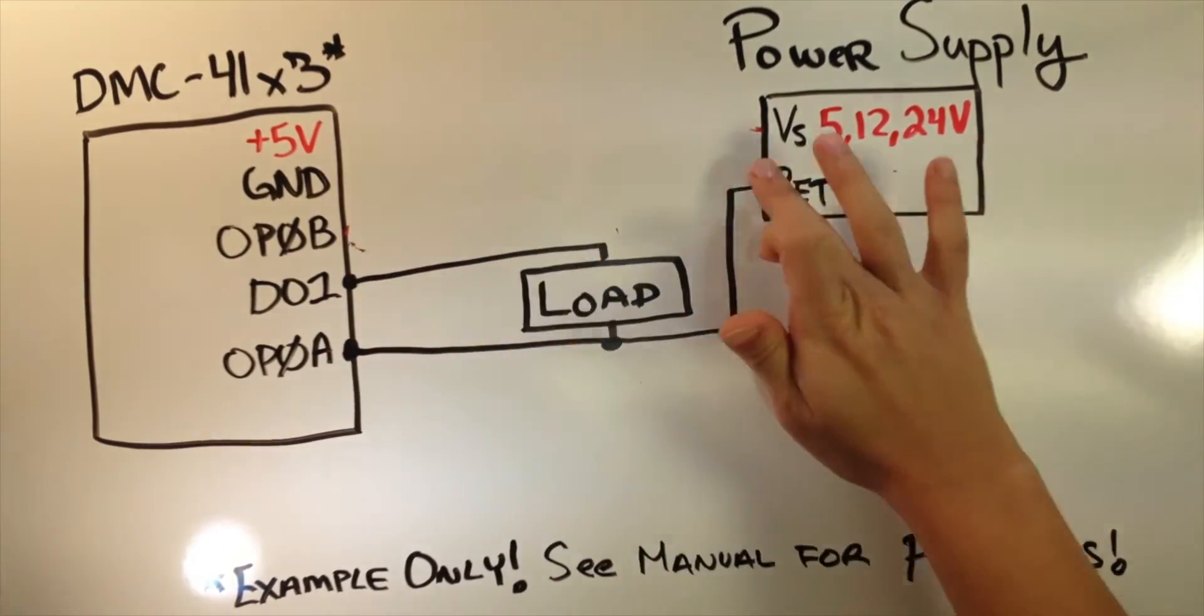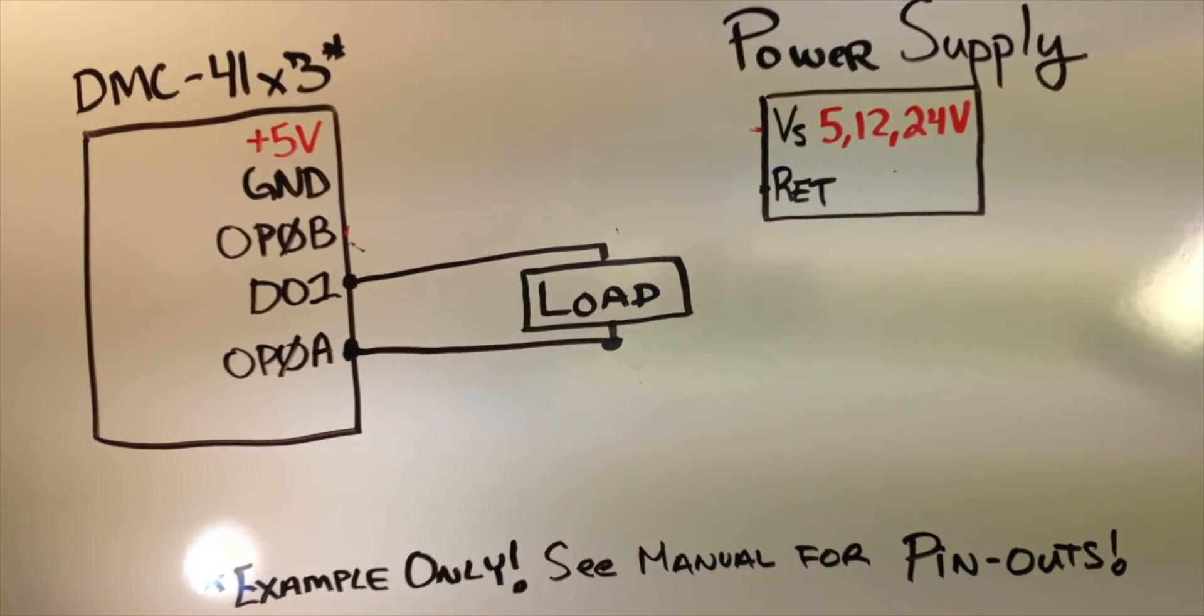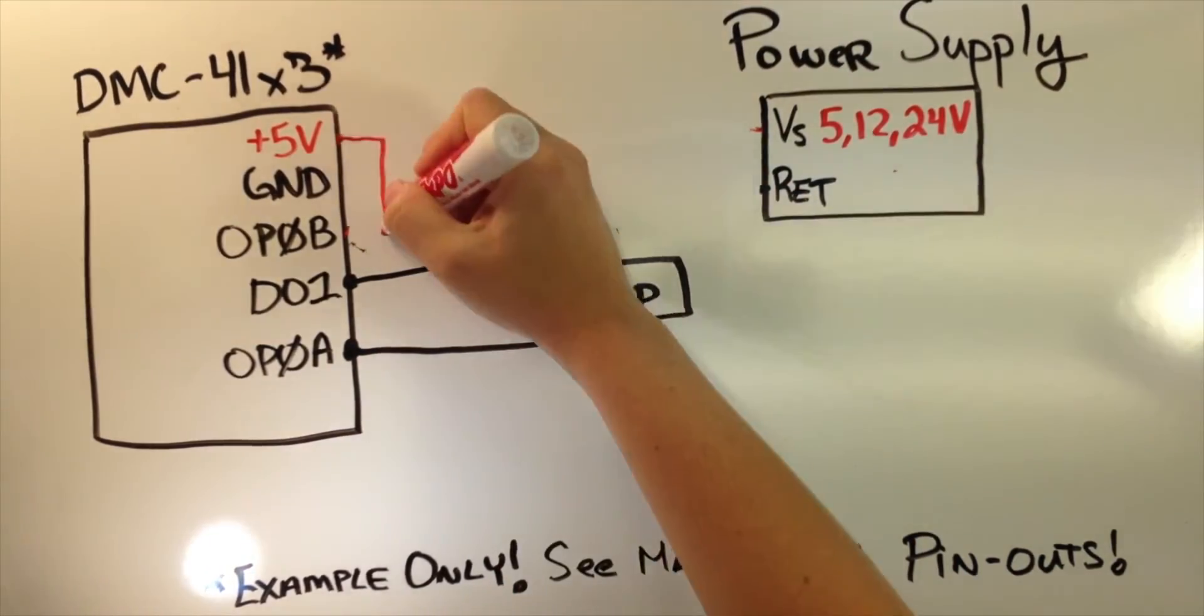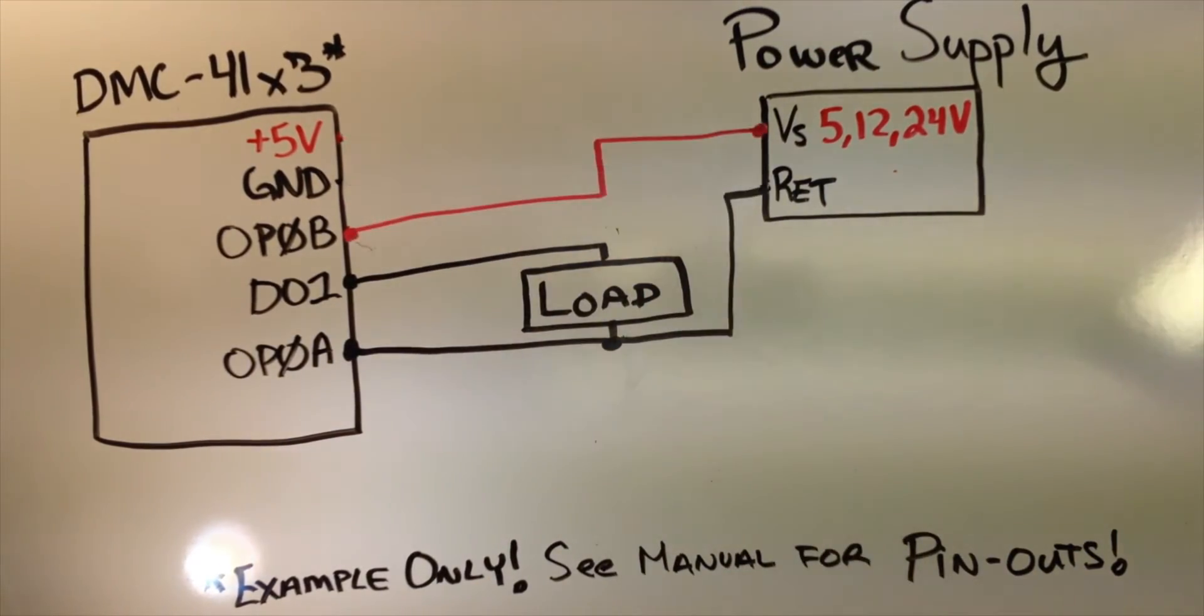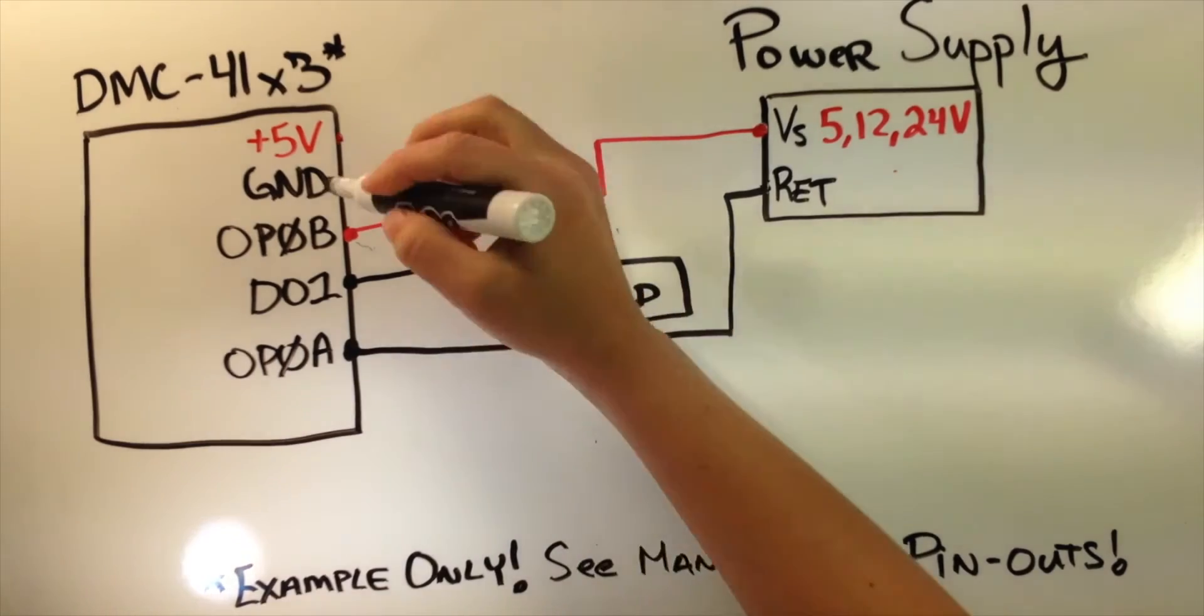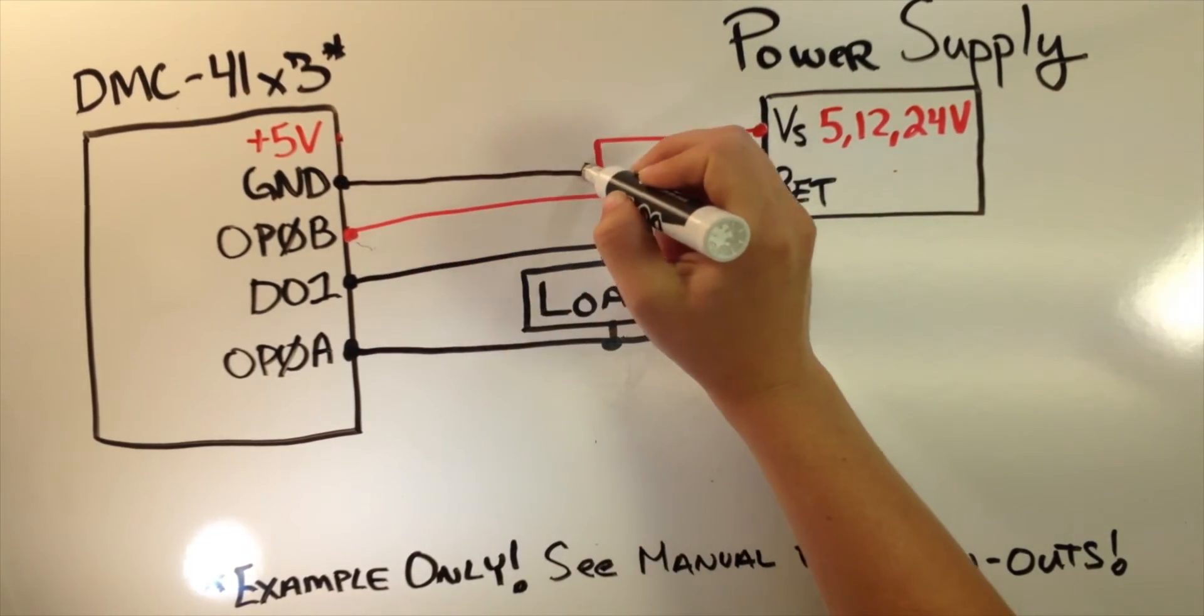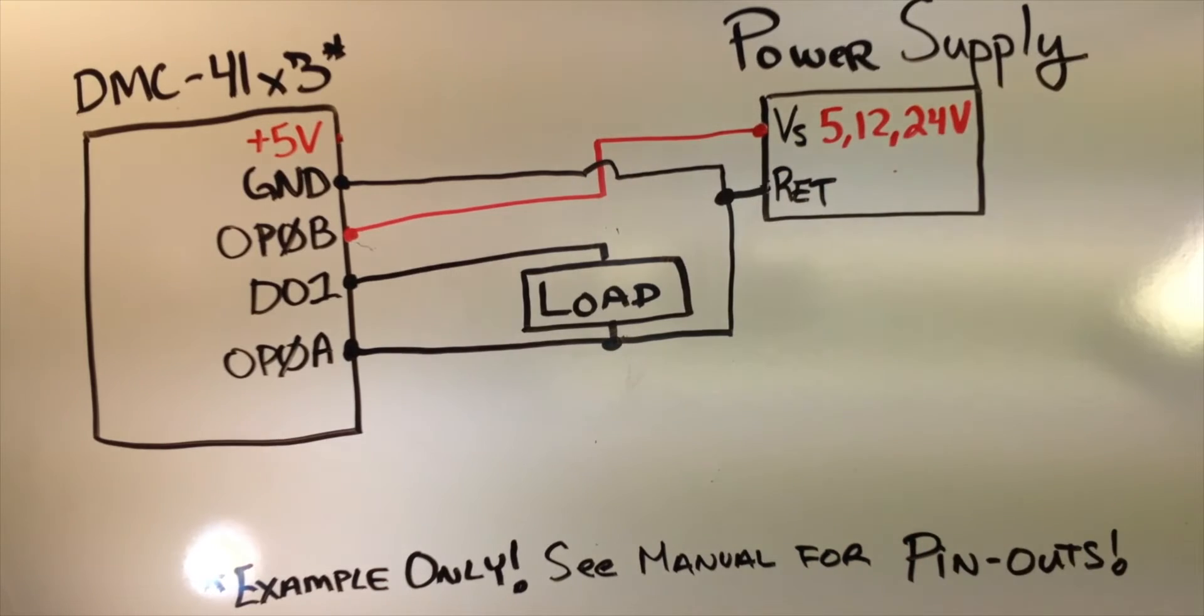Opto-isolation can also be bypassed, meaning the outputs can be powered using the plus 5 volt and the ground reference on the controller. Even with an external supply, one may inadvertently bypass opto-isolation by tying the ground of the controller with the output supply return.